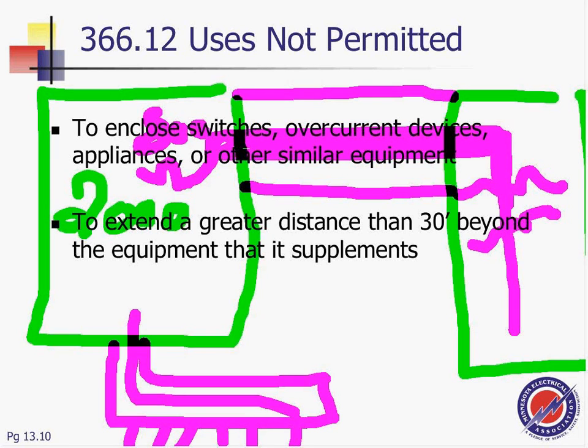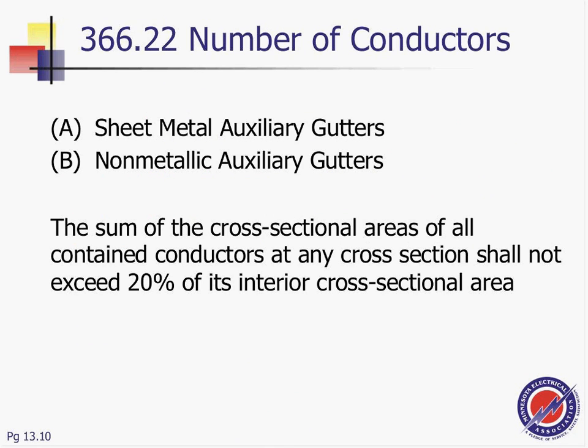So, how many of you have used gutters? Few. Okay, it's handy, especially on major equipment like 4,000 amp switchgear, guys. Pulling a 1,000 amp feeder, and buying another piece of equipment to extend the switchgear, takes a few modifications, but it's slick. That's one end. On the other end you pull your circuits in and just pull branch circuits and feeders and so forth. Number of conductors, sheet metal gutters and non-metallic.